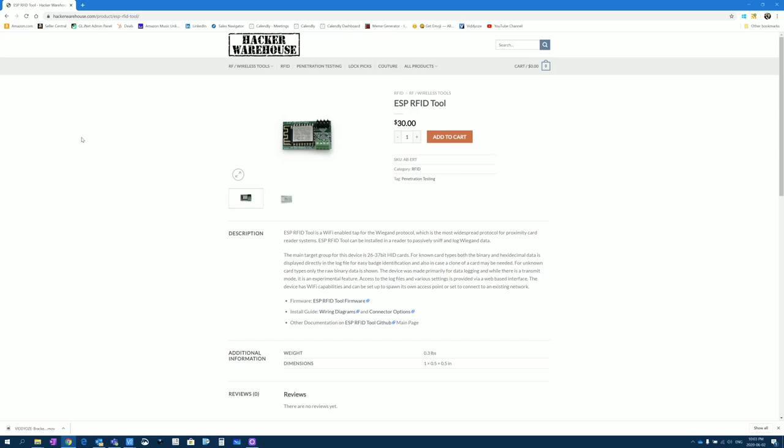And there's other devices out there. There've been improvements. There's a device called the ESP key. That's from another group, a consulting group, an ethical hacking group. And that's a really nice device. It comes with an embedded web page. It broadcasts an SSID for Wi-Fi. So it's incredibly simple to use. I purchased one myself to test it, and I was able to install it, see the data, do a replay attack, and open the door through one of these sniffing devices in less than 5 minutes.